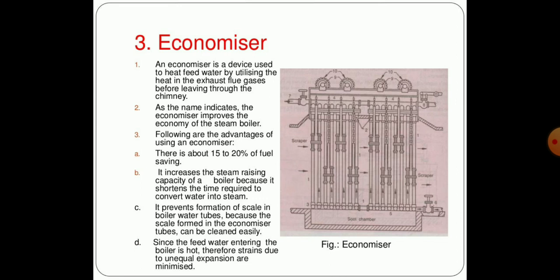Now economizer is another important accessory of the boiler. Economizer is a device used to heat the feed water by utilizing the heat in the exhaust flue gases before leaving the chimney. As the name indicates, the economizer improves the economy of the steam boiler. It has the advantage that waste flue gases are used to heat the water again. It increases the steam raising capacity of the boiler because it shortens the time required to convert water into steam. Also it prevents the formation of scale in the boiler water tubes. Any scale formed in the economizer tubes can be cleaned easily.